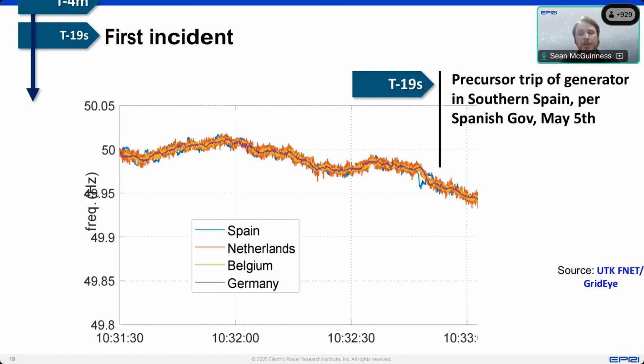It doesn't seem to be very large in magnitude, the frequency drop. The bar here is a little bit to the right of where the frequency dip happened, but hopefully you can see it in blue. So it was relatively small in magnitude, maybe 0.01, 0.02 hertz of a drop. So it's relatively easy to miss in this chart. But this was really the first event that occurred. So if this kicked in, this may have activated or triggered other ancillary services to rectify it. We don't know, but this is where the actual event itself began to occur.